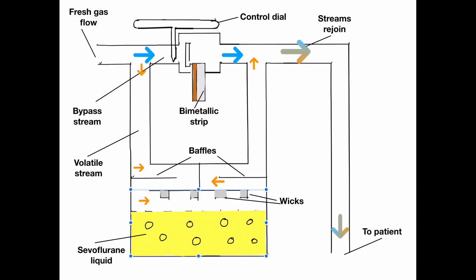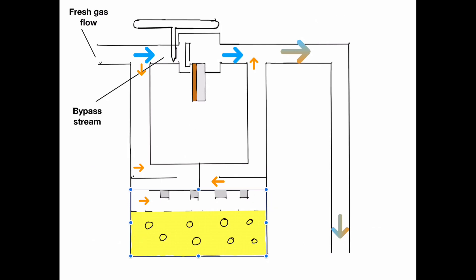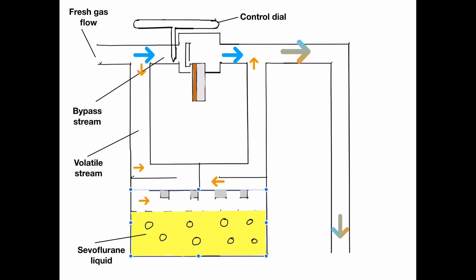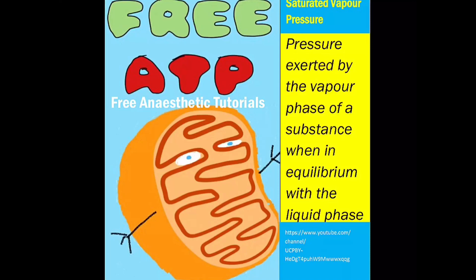As you can see there are a number of key components shown on this slide that we think are important. The fresh gas enters the vaporizer and is split into either the bypass stream or the volatile stream. The splitting ratio, which describes the proportion of fresh gas that enters the volatile chamber, is controlled by the splitting valve, and this connects and is calibrated on an external dial. The anaesthetist can use this dial to dial up the desired splitting ratio. The gas flows entering the vaporization chamber encounter liquid volatile agent, and as it travels past the volatile, evaporation occurs and this volatile will then join the gas flow to the patient. The vaporizer relies on the gas leaving the vaporization chamber being fully saturated and therefore exerting the saturated vapor pressure of the anaesthetic agent.